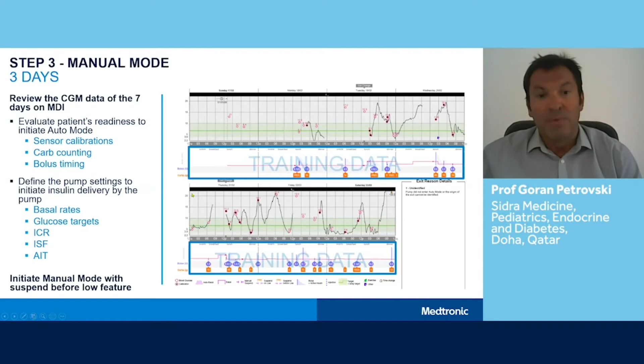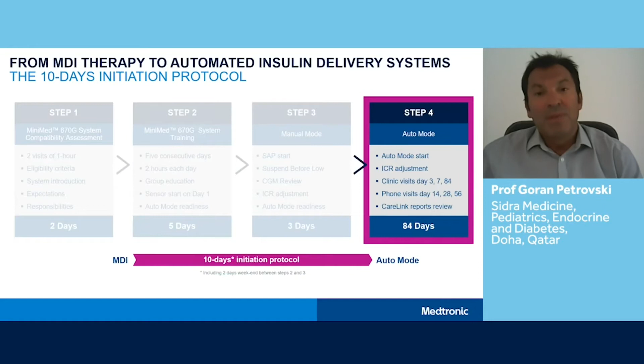Then we define the pump settings based on our regular clinical settings. We have the auto generator, which generates the pump settings, and then we do fine tuning if needed based on the previous 7 days of CGM data on MDI. So we do the basal rates, the glucose targets, the carb ratio, the sensitivity, and the active insulin time, and we initiate the manual mode with the suspend before low feature. The patients stay only 3 days in the manual mode, and we found that it is enough to initiate the auto mode. So this is step number 4, which means that we initiate the auto mode.